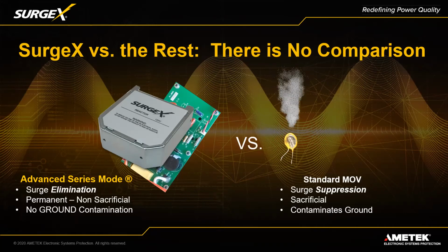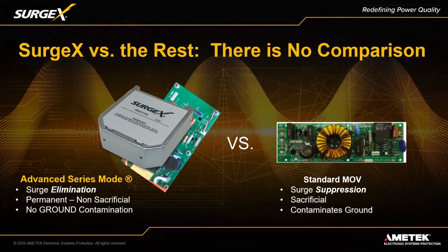It's not a surge elimination device, it's surge suppression. So it takes that 6,000 volts and brings it down to a number less than 6,000 volts, but it's not zero let-through like SurgeX is. And they also contaminate ground.